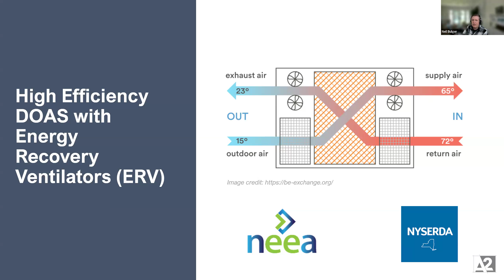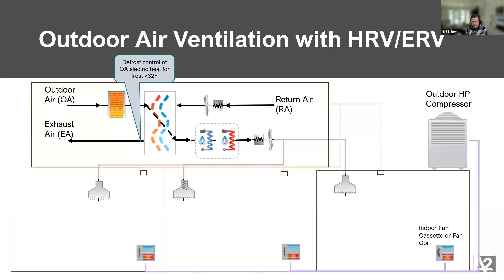One piece of that research was the challenge of frost building up in an ERV. In certain instances, when outside air is very cold touching these metal plate and frame heat exchangers, you can create ice. Certain products use electric resistance heating to melt that ice. Depending on which product you buy, you may or may not have this electric heating device.